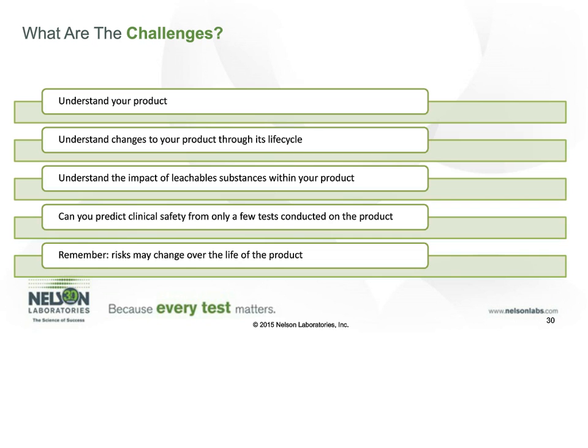We have a history of safe medical devices using those tests, but now that we're using chemistry and we can look at published data to come up with a risk assessment on each compound, or mixtures of compounds, that come off a device, we're starting to reevaluate the sensitivity of these animal tests and other in vitro tests. Are they as good predictors as we originally thought? We're just barely scratching the surface of comparing the results of these material and chemical evaluations to the history of animal tests. My assumption is that we might come up with more sensitive and better predictors of safety by looking at the chemistry and material of devices than we would by just injecting into a guinea pig and sitting back to watch what happens.